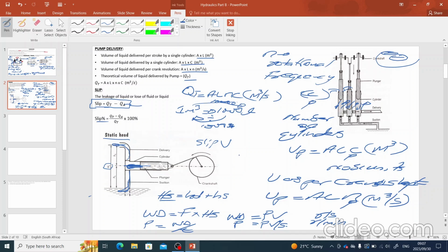Now, these are the formulas that we'll be working with to calculate whatever they want us to calculate. Now, in calculating pressure on your hydraulic hoses, pressure equals density multiplied by gravity multiplied by height. And the height there can be the static head, right?